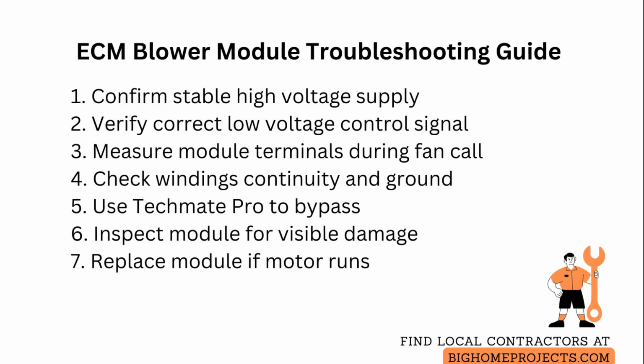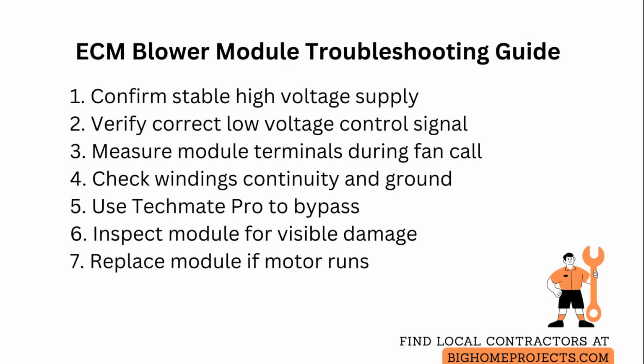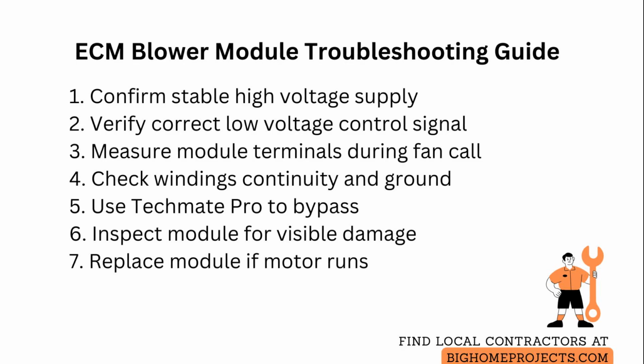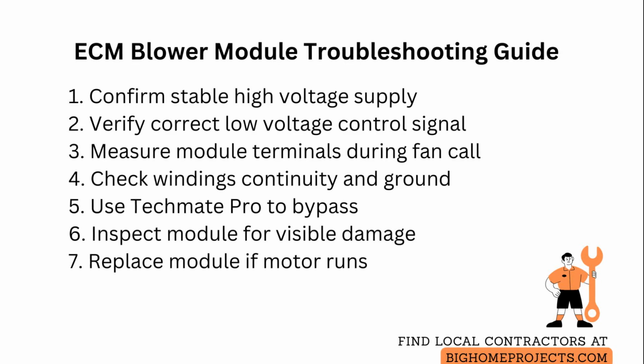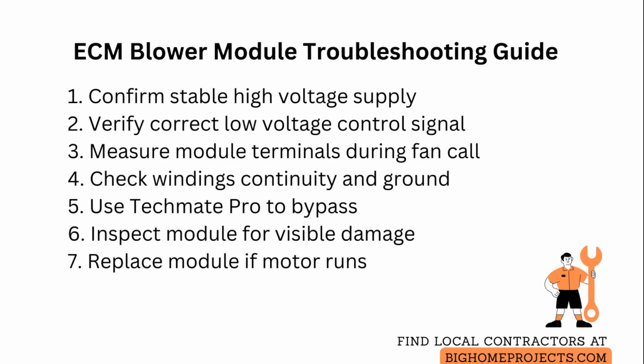Inspect the module for burned components, swollen capacitors, or cracked solder joints, and gently wiggle connectors while testing to reproduce intermittent faults. If the motor runs normally when driven directly and wiring and supplies are correct, then replacement of the module or hub is warranted.